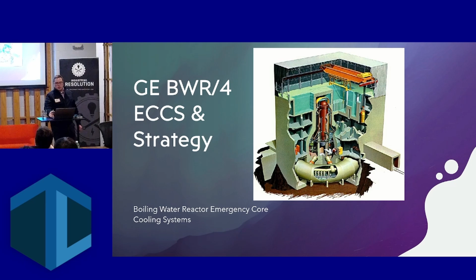We've got various systems that are relied upon in order to add cooling to the core. The concept I said earlier, that no single failure can cause or prevent a safety actuation, is true here, because what I use is a concept of diverse and independent methods of getting coolant into the core. Some of these pumps are steam driven, some are electric driven, and if they're electric driven, they're driven from different sources, so that any one failure of a source doesn't knock out all my capability of doing any cooling.